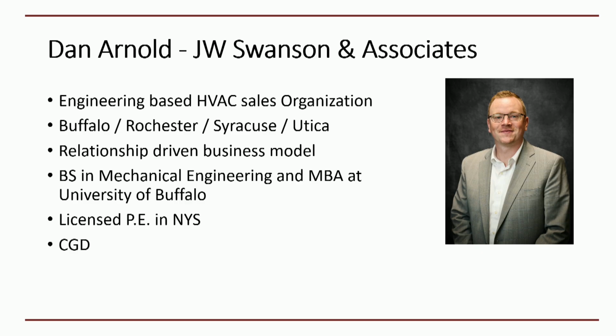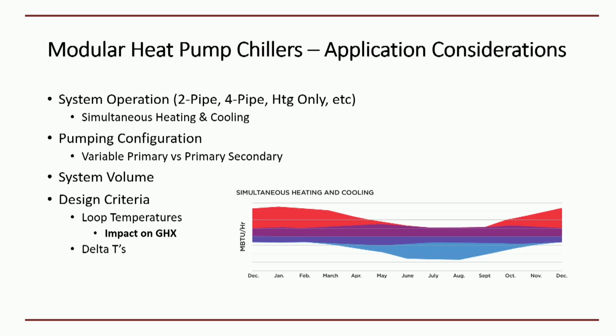I am a licensed PE and CGD. Again, relating this back to the ground loop is really what we're here for. So when we talk about the modular heat pumps and heat recovery systems, there's a lot of ways to skin that. There's 2-pipe, 4-pipe. This is really what we're talking about in the building system itself. Just when Tim got finished talking there, he's talking a lot about 6-pipe, and that's what we're here to talk about today. So just to recap, 6-pipe is you're looking at 2 source pipes, 2 chilled water pipes, and then 2 hot water pipes, which would inevitably feed a 4-pipe system in your building. That's really the core of what we're here to talk about today, but there are a lot of ways to do modular systems, and I just wanted to make sure that was aware to everyone.